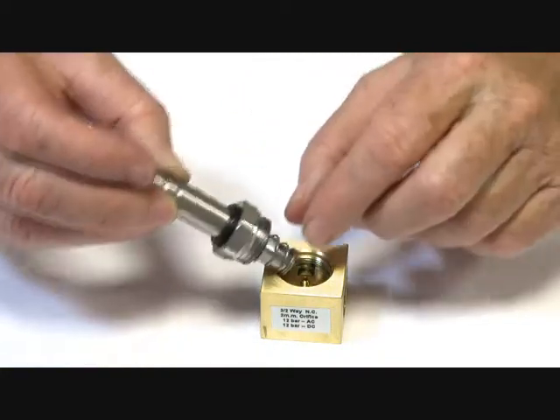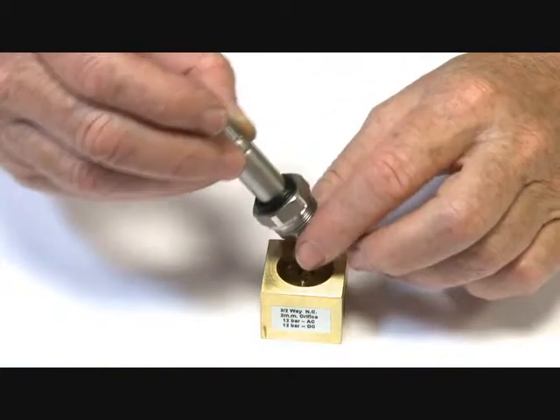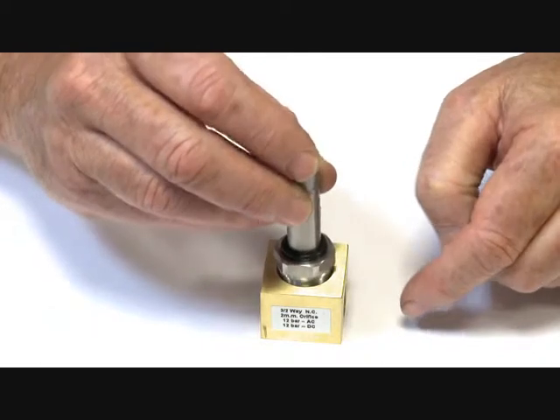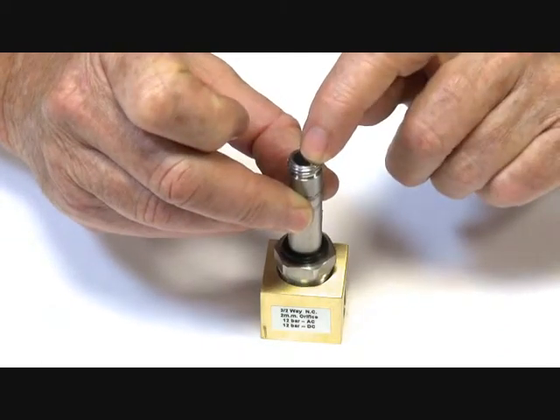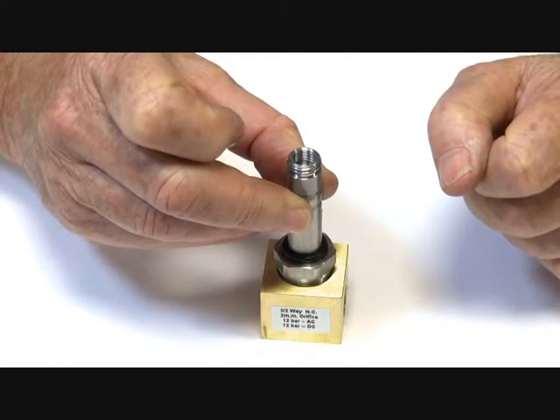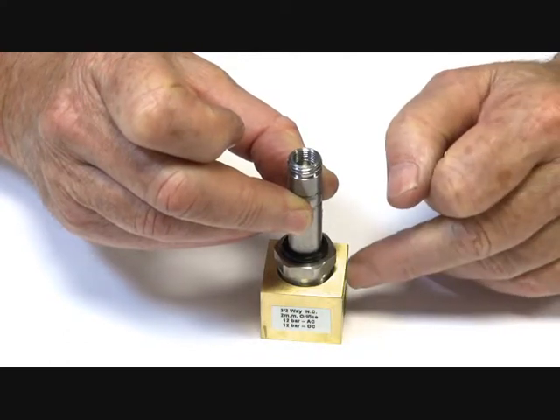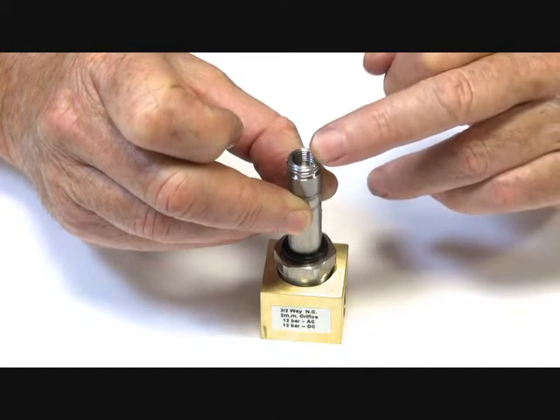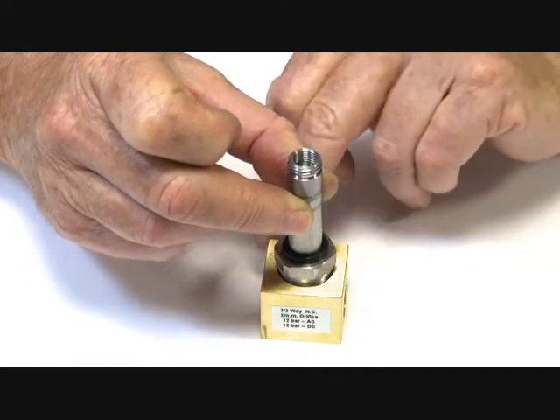When it comes back down and seals off the inlet, the downstream pressure is relieved back up through this exhaust port. So this is a three-way normally closed power to open valve. In the closed position, the downstream pilot is connected to the exhaust and the flow is cut off.